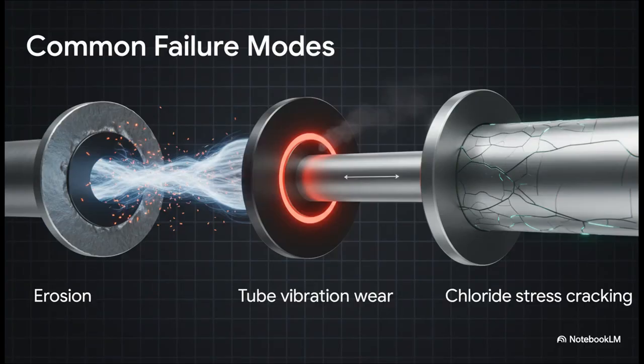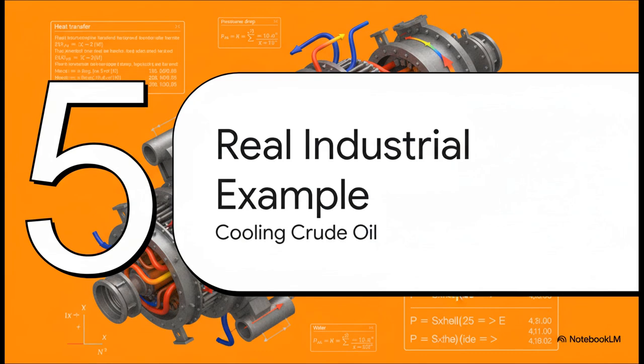And it's not just about fouling. We also have to design to prevent other common ways these things can fail. If your fluid velocity is too high, you can get erosion, especially right at the tube inlets. Unsteady flow can cause the tubes to vibrate and literally wear themselves out against the baffles. And for some materials, like stainless steel, if you have the wrong mix of chlorides and temperature, you can get catastrophic stress cracking.